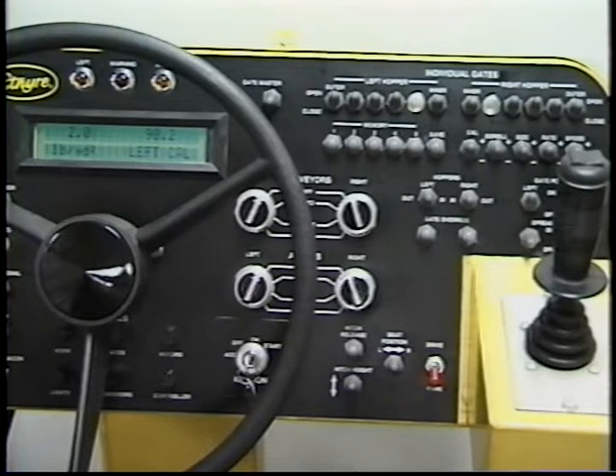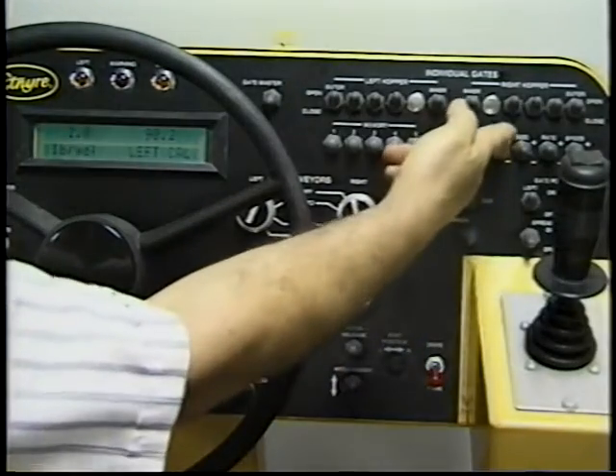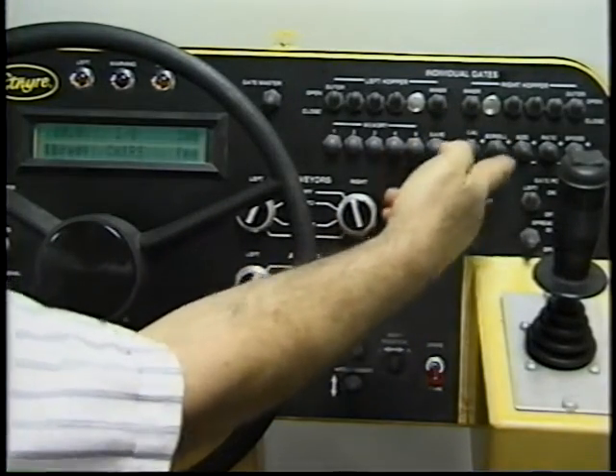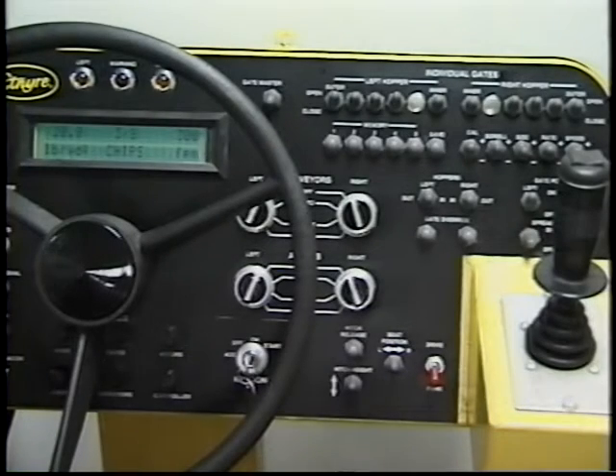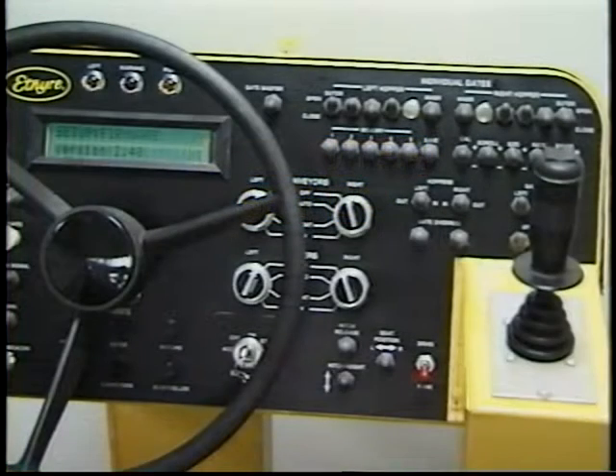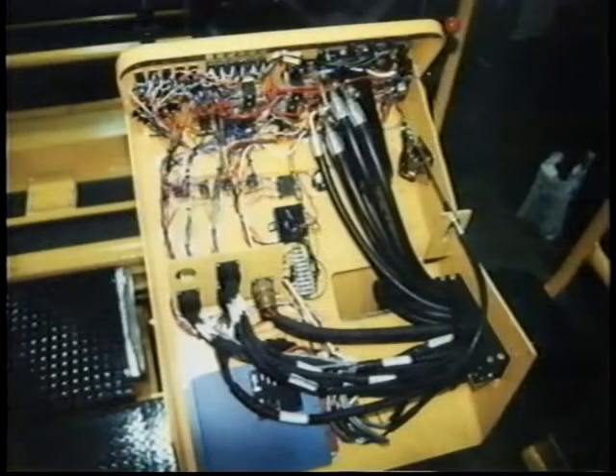The calibration process is permanent, meaning when the machine is powered down, the changes will be saved for the next time the machine is put to use. The computer must be set up and the various sensors and valves calibrated for the particular chip spreader that the computer is installed in. This is normally done at the factory, and the settings are retained in the computer's non-volatile memory.